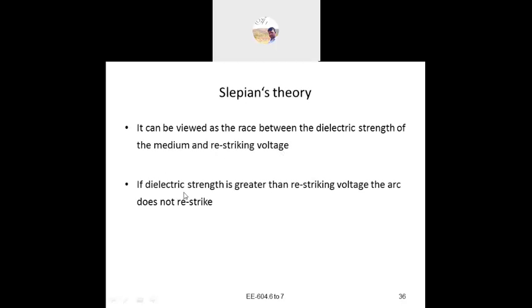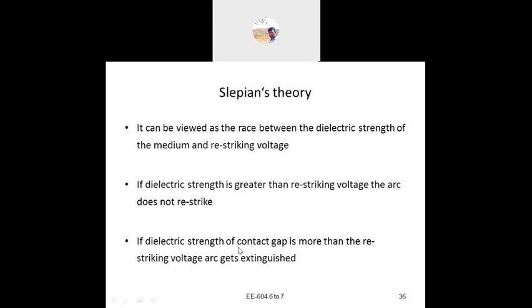In this type of theory, we are taking the dielectric strength as greater than the restriking voltage. The arc does not restrike, that is, it will not reappear. If the dielectric strength of the contact gap is more than the restriking voltage, the arc is extinguished. Suppose there are two contacts with some medium between them, and the arc is induced.